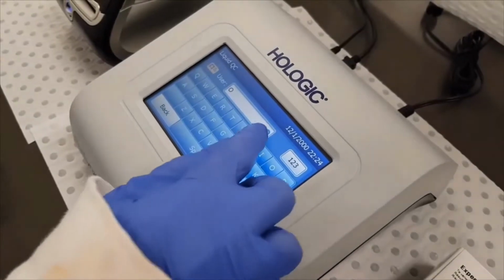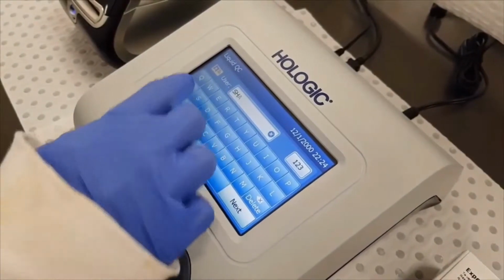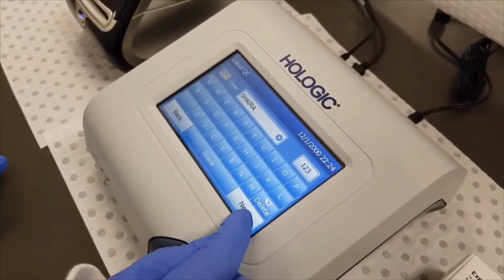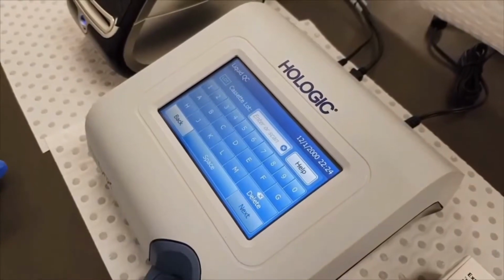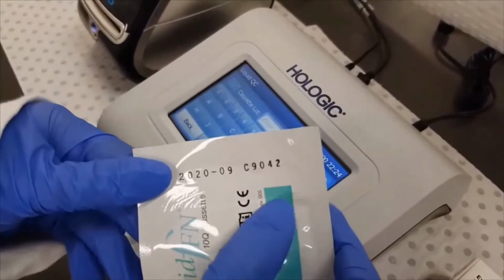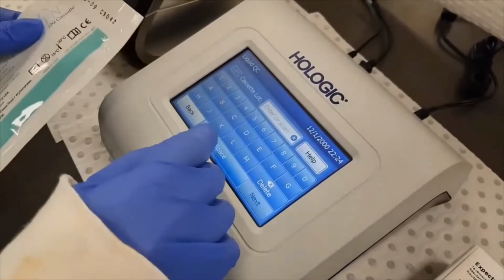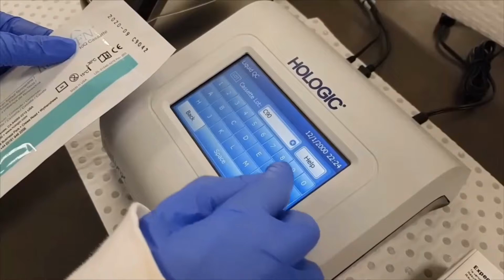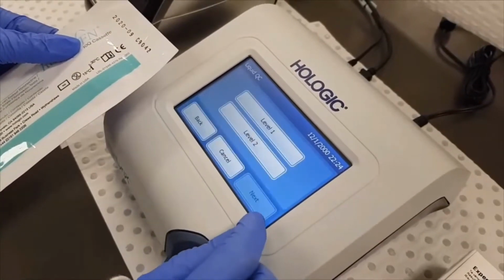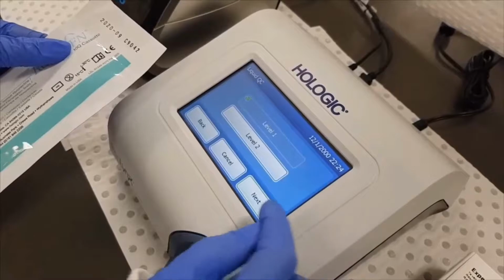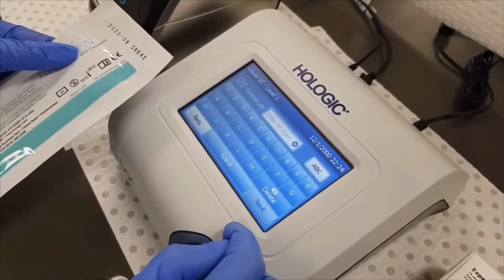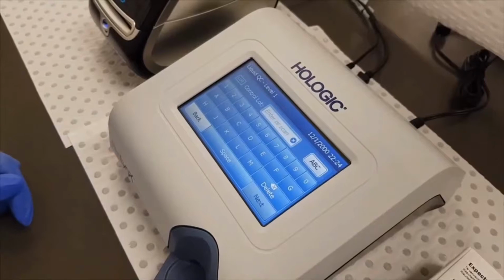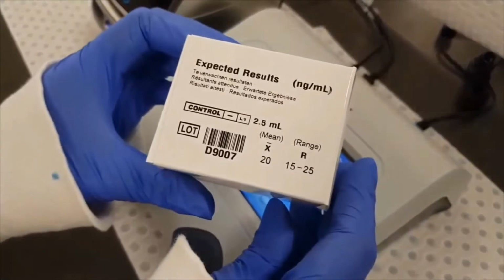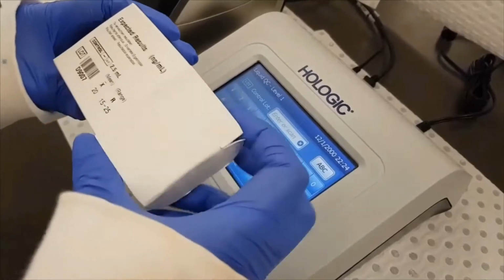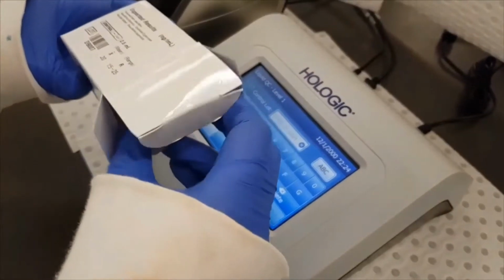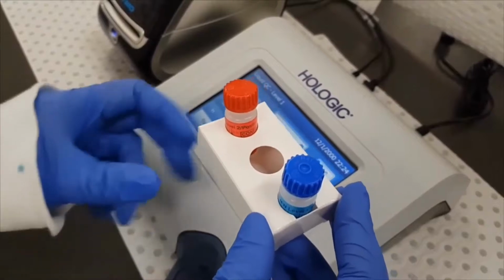Run liquid controls by first entering your user ID. Enter the cassette lot number found in the cassette packet and ensure it is within the expiry date. Start with running the first level of control and press Next. Carefully unpack the control reagent kit box containing the level 1 and level 2 controls. This is a negative and positive control respectively.